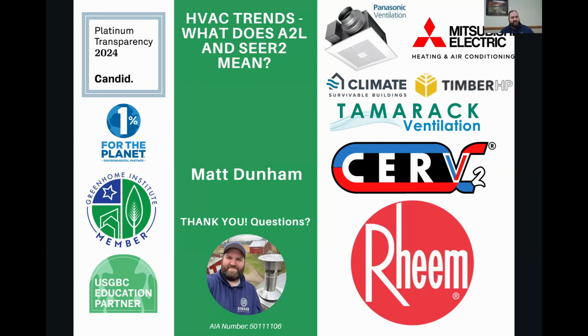I've actually had the opportunity to charge a system properly with it, come back a year later and examine that system, and it still was dead on the money, even though different things had changed. There's a different day, different weather, different indoor load. The app was right on day one, and it was right 365 days later. So if someone's just putting a regular set of gauges on and saying, "Yep, looks good," I would ask questions. What's my superheat? What's my subcool? How do you know that it's properly charged?